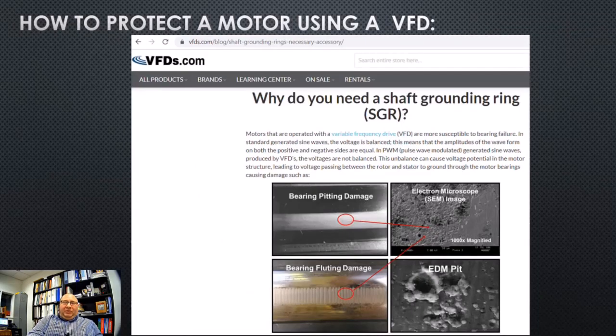So this is what we need to know about grounding rings, okay? This is something that you're going to see on your STAR exam when you're going to be in 5th year. It's an add-on that we could put on to variable frequency drive motors. VFDs are more susceptible of obtaining bearing failure, as the previous slide was saying. Right, it's generated by the sine waves. The voltage is balanced, which means that the amplitudes of the waveform on both the positive and negative sides are equal. So in pulse width modulation generated sine waves produced by VFDs, the voltages are not balanced. Right? That imbalance from pulse width modulation is how we rectify or make a motor spin at different hertz.